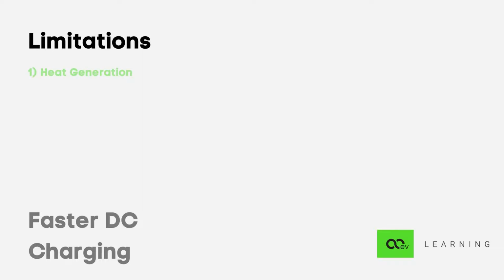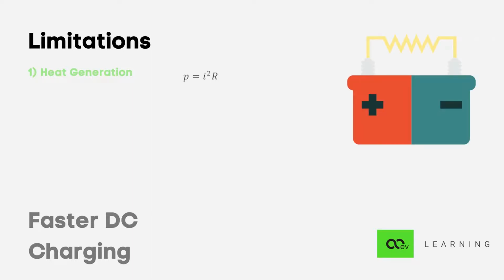First is heat generation. High current supply to the battery pack generates heat due to the internal resistance of the battery cells. It mainly depends on the cell chemistry and internal construction of a cell. The heat loss is represented as I squared R. This says that losses become 4 times every time the current is doubled. At higher current levels, these cells act as a resistor and energy is lost as heat. This heat generated in the battery pack leads to loss of active materials. Thus, frequent use of fast DC charging stresses the battery pack and results in degradation of cell life.